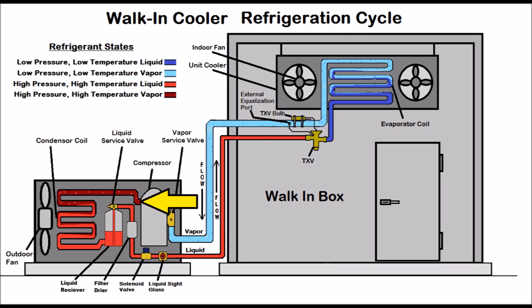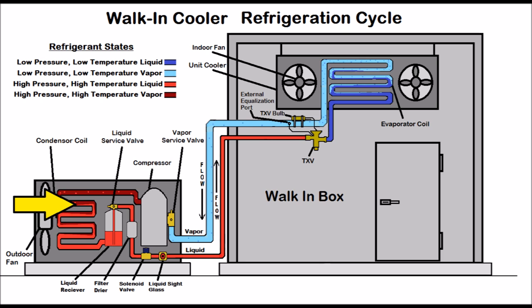Temperature follows pressure. Where it comes out of the compressor, that's called the discharge line. It rides the discharge line until it goes into the condenser coil, where it's rejecting heat to the outside air. It starts rejecting enough heat until it ends up turning into the saturated state — that's where liquid and vapor both exist at the same time. That's the dark red and light red colors shown in the condenser coil.